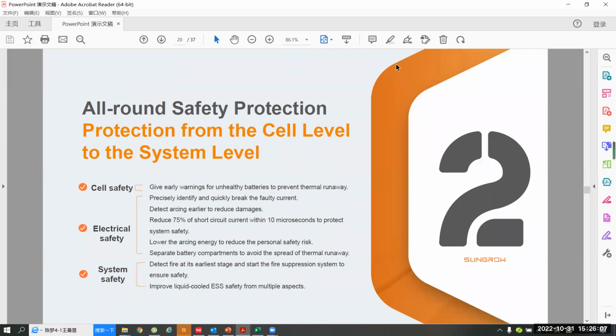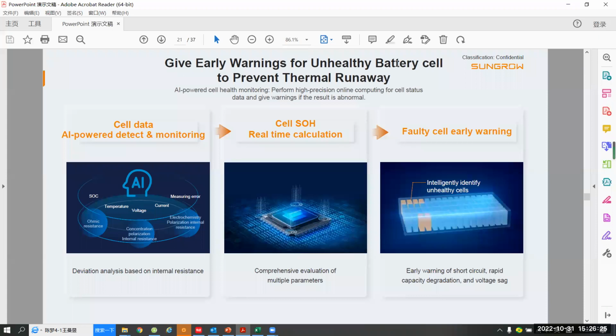It is from the cell level to system level, which covers the cell safety, electrical safety, and system safety. For the cell safety protection, it concerns cell data monitoring, cell status evaluation, and then locating the failed cell and doing the early warning. On cell data monitoring, the BMS will detect and monitor many parameters of the battery cell, such as the cell voltage, cell current, cell temperature, and cell resistance. Through all of these parameters data, the BMS will calculate and evaluate the battery cell status in real time. And then it can locate the faulty cell and do the early warning.